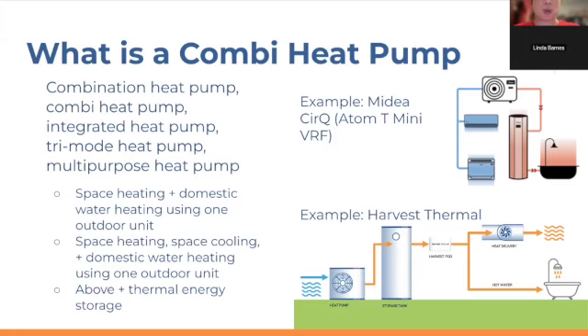Typically, that is in the form of a fairly large tank of water, like 80 or 120 gallons, meaning that the outdoor unit can charge up and heat up this tank of water, and then the air handler can draw heat from this tank of hot water even when the outdoor unit's not running, so that there's some decoupling between when heat is being used and when it's being generated by the outdoor unit. And typically, the tank sizing results in a thermal energy storage duration of somewhere in the neighborhood of 30 minutes to maybe an hour or two, depending on how cold or how hot it is outside.